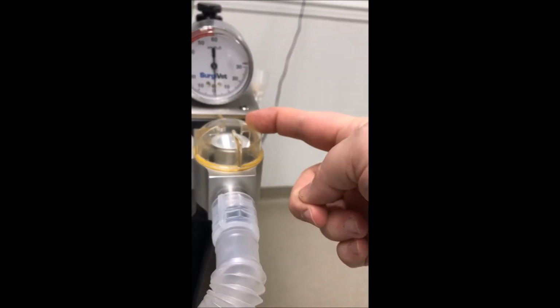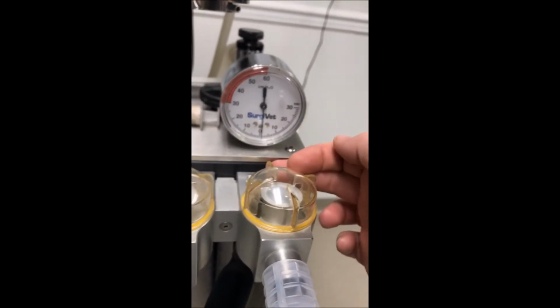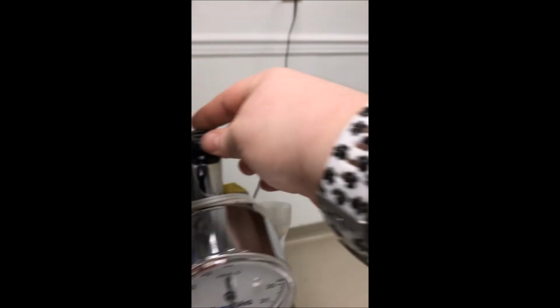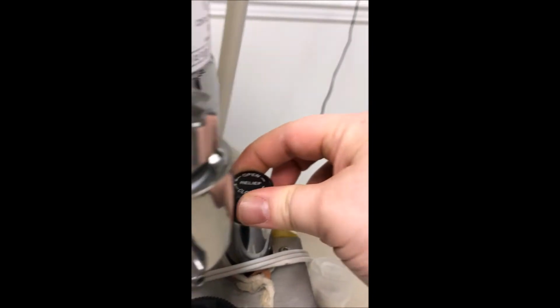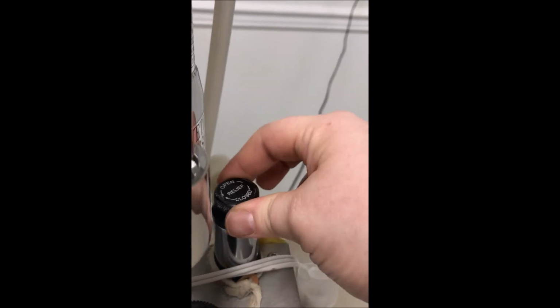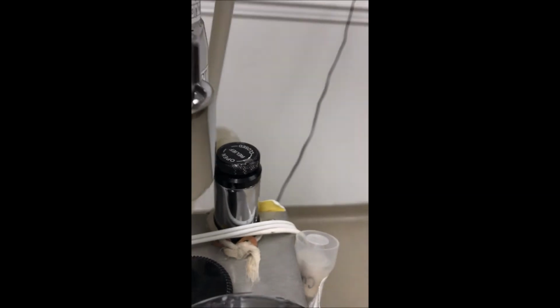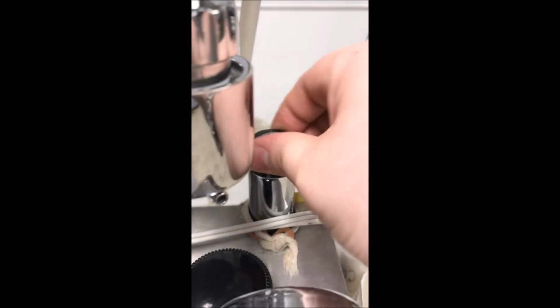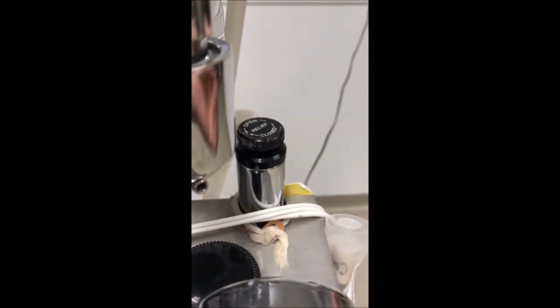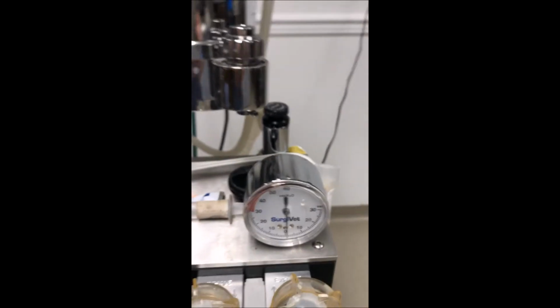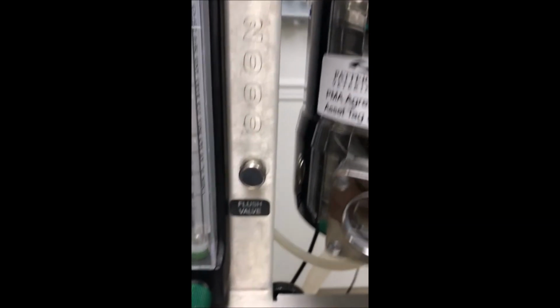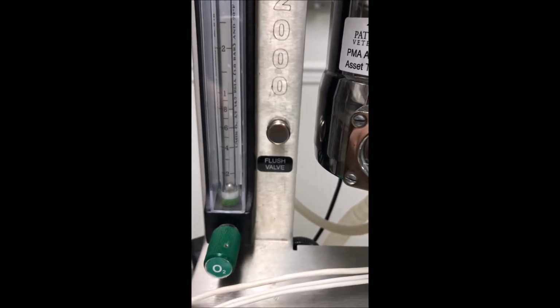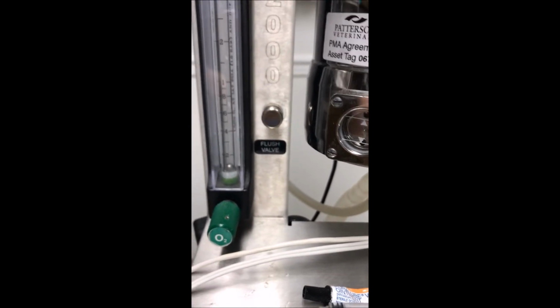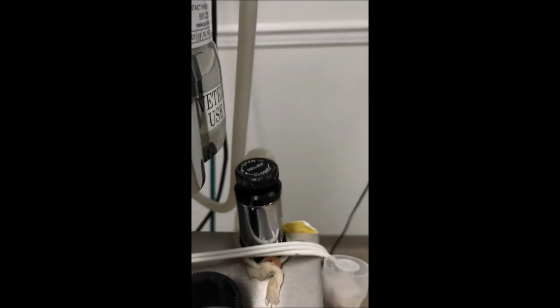Then when the patient breathes out, this unidirectional valve will open for exhale. We have our pop-off valve back here. We must always leave this open. If you have it closed down, this will allow gas to build up and can actually cause patient injury. So make sure that your pop-off valve is open. If you were to use your flush valve over here, say you wanted to fill the reservoir bag or to do a test on your machine, you must first close off your pop-off valve.